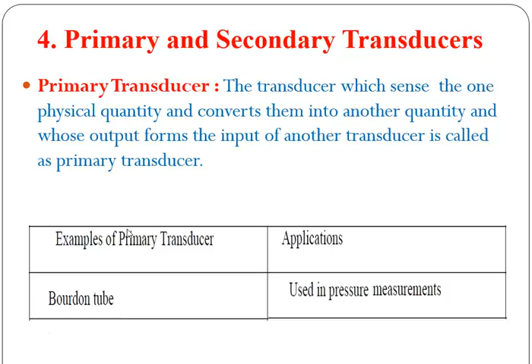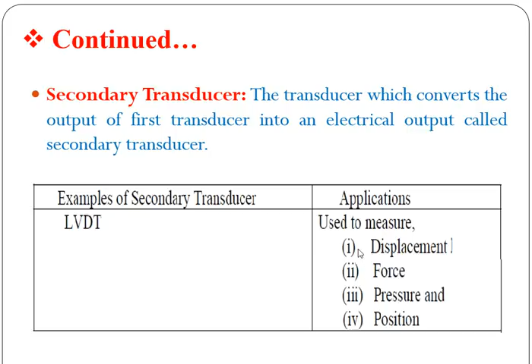So in this example, the Bourdon tube converts the physical quantity into some mechanical movement, so this is the primary transducer. The output of this Bourdon tube is applied to an LVDT, which converts the output of the Bourdon tube into a direct electrical signal. So in this application, the Bourdon tube works as a primary transducer and the LVDT works as a secondary transducer. Combined, we can say this is only one transducer - a pressure transducer for a pressure application. But this LVDT can be used for different applications also, as we have seen earlier.